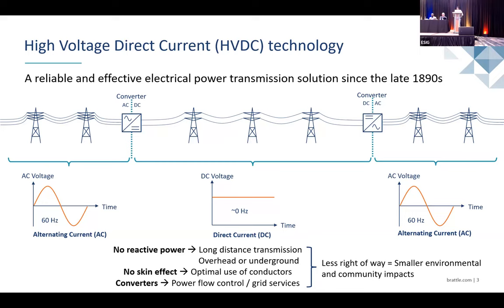And further, because of the zero frequency, you also don't have a skin effect. When you don't have a skin effect, again, you can use the conductor optimally. And also, losses are reduced. And at the same time, these converters, the key components in HVDC, are converting AC to DC, and at the same time, they can precisely control power flow in the DC circuit. That makes HVDC so attractive.